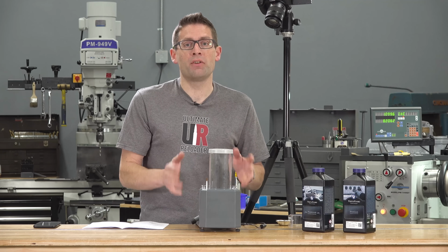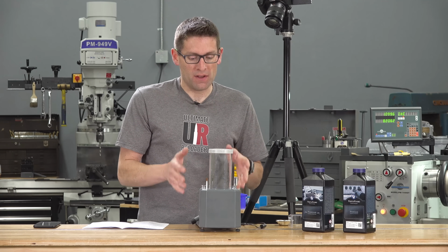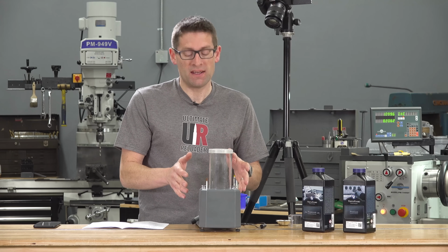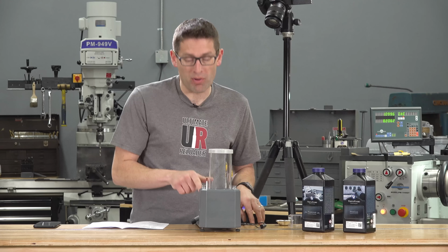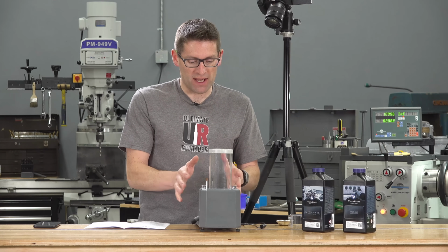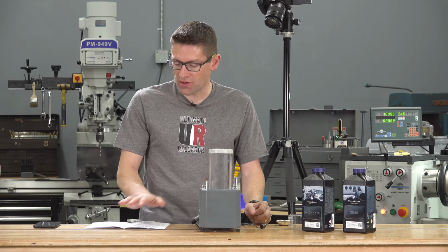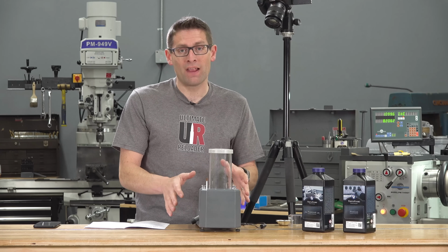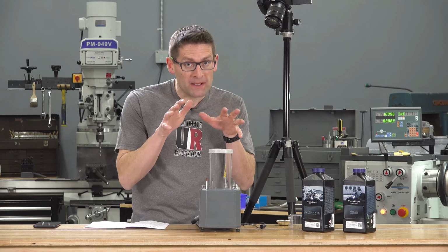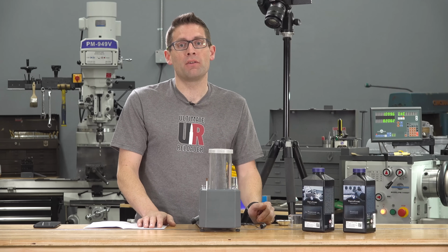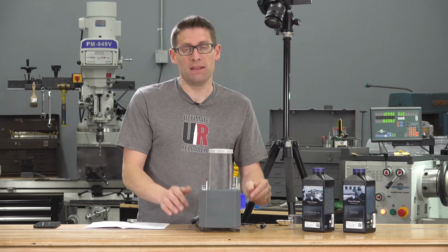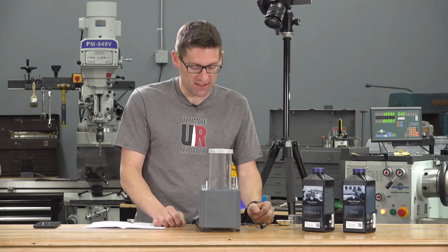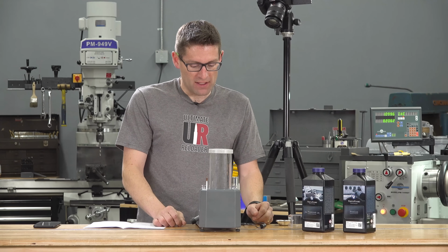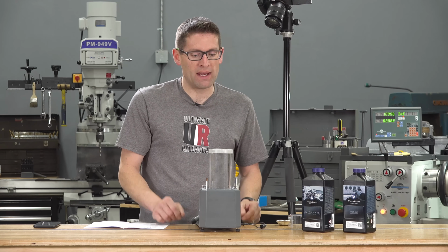Now, a couple other notes about setting up the unit. These are precision scales and they need to be leveled. There's an integrated bubble level here, and I took the time to very carefully get that centered. The instructions state that if you're not completely level, you can get up to a 0.3 grain offset in the charge weight and inaccuracy, and obviously that's not what you want. Okay, so the machine is now set up. Now we can add some powder.